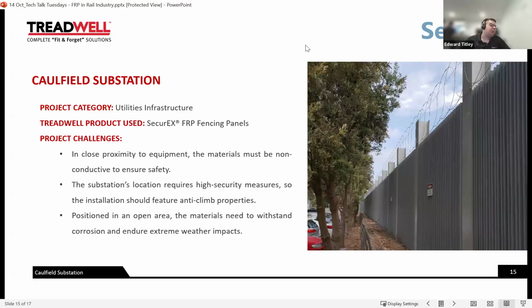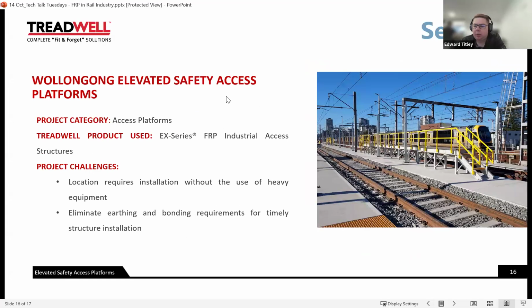Caulfield substation, this is one of our fencing products, a complete FRP fencing system. The client here was having some issues getting the isolation distances they needed to be able to use a steel fence. FRP fencing resolves that because it's non-conductive, significantly reducing the likelihood of arc flash, stray currents, those sort of things. So we can condense the footprint of the substation. We can also install the panels with a smaller crane because they're a lot lighter. In this instance, I think just a truck-mounted hire crane was used to lift these panels in, a lot smaller than having a larger crane. And this is where the graffiti aspect came from as well, being able to clean off the graffiti very easily without any damage to the FRP.